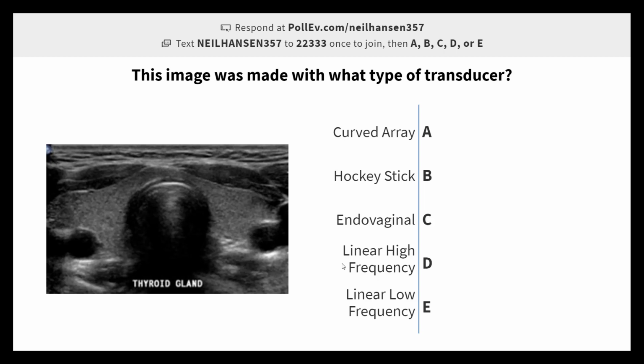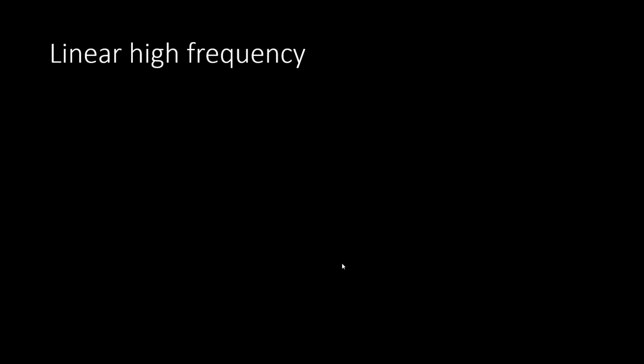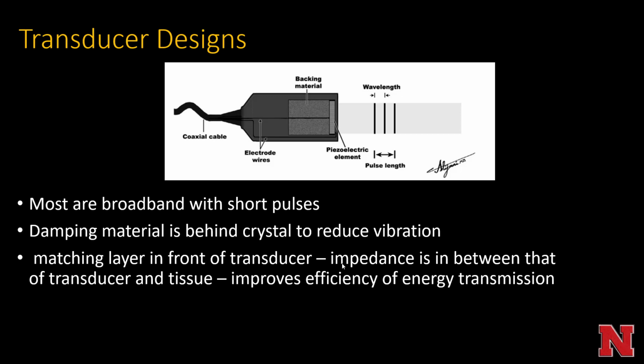Thyroid ultrasound is done with a linear high-frequency transducer. High frequency works really great for things that are superficial, like the thyroid gland. Transducer design: most are broadband with short pulses. Damping material is behind a crystal to reduce vibration, and there's a matching layer in front of the transducer. Impedance is in between that of the transducer and the tissue, which improves the efficiency of energy transmission. That's all basic engineering stuff, which I don't understand that much.